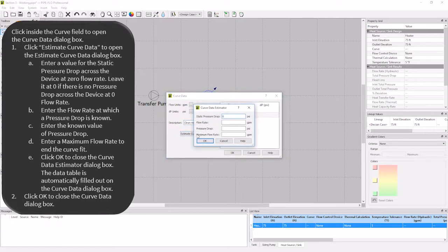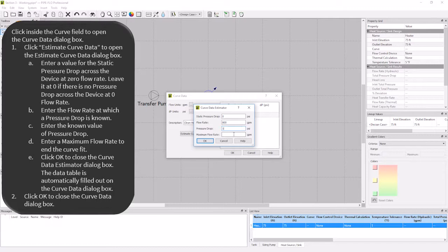I will enter in my static pressure drop to be 0 psi, my flow rate to be 800 gpm, the pressure drop at that flow rate to be 5 psi, and the maximum flow rate to be 1200 gpm.